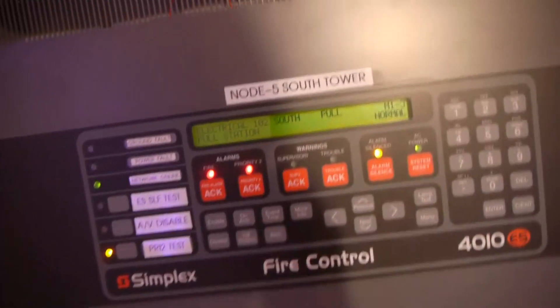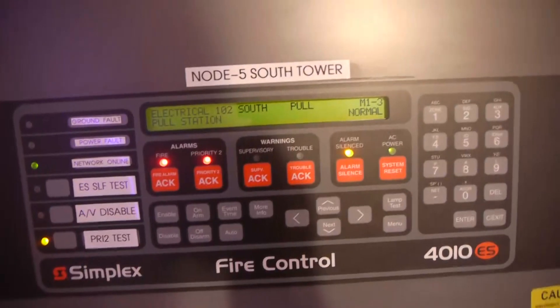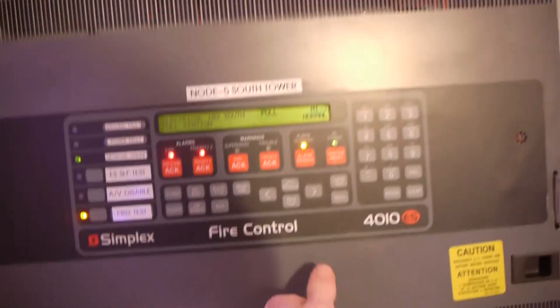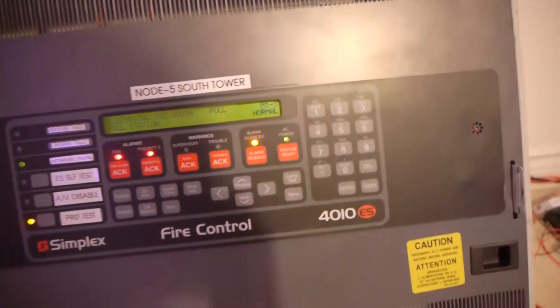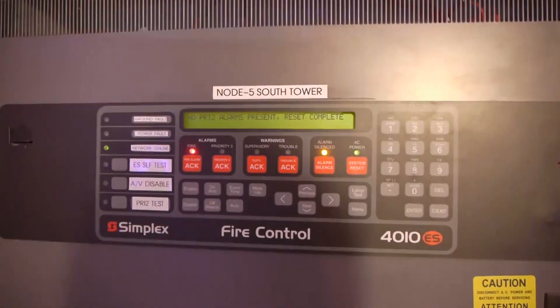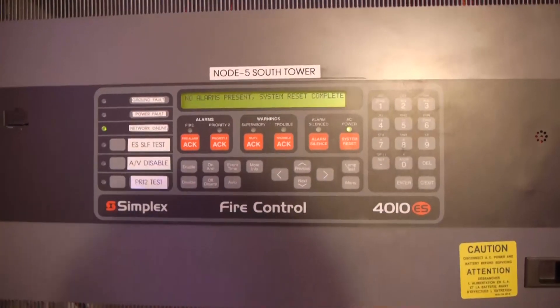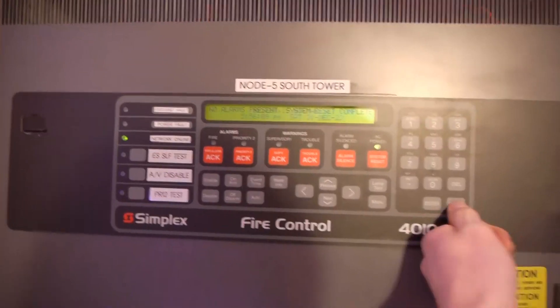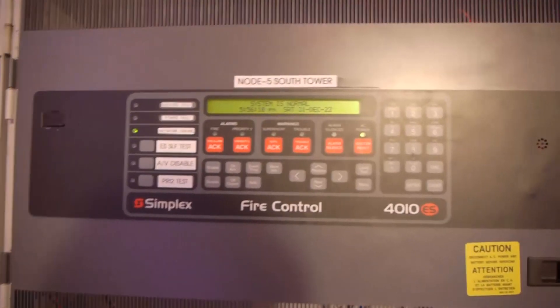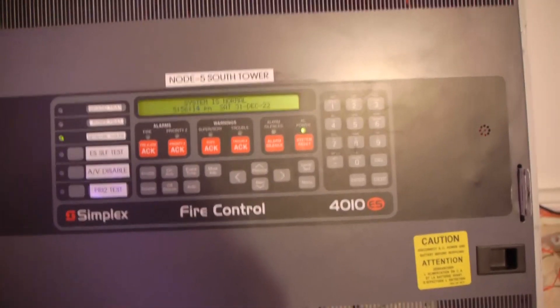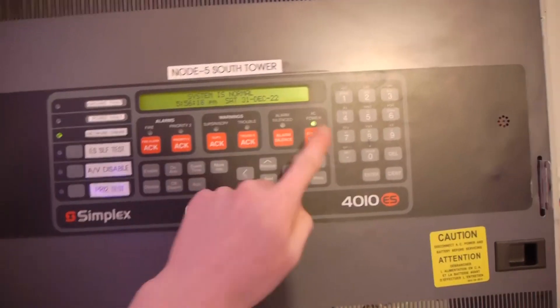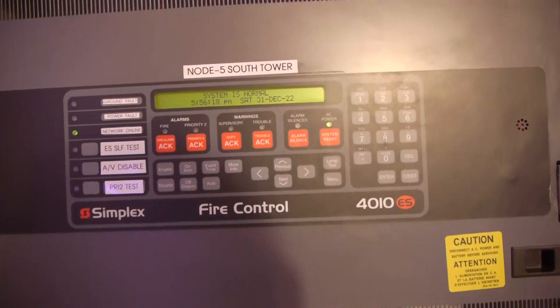And now we have selective silence. Let's see, is this a 9000? Yes, this is a 9003. And if we look right here, you can see exactly what device that was. M1-3. Alright, and now we can go ahead and reset. Now it says no priority two alarms present, reset complete, because I have a program to only do a priority two reset, which is separate than the fire reset if there's a priority two event. So because there's a priority two event, it automatically reset that when we did a system reset. So there we go.